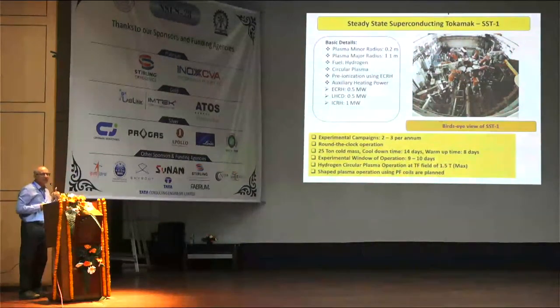This depends on the capacity of the cryo system, and also the need not to allow thermal stresses to build up. The warm-up time is about 8 days. So effectively, we get an experimental window of operation each time for about 9 to 10 days.